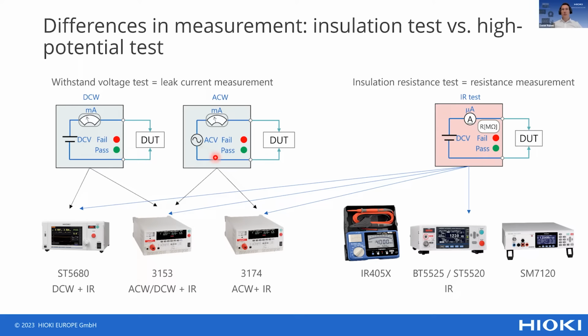While with the withstand voltage test, we have either a DC voltage or an AC voltage being applied to the DUT. We simply only look at the current. So the current resolution is the main interest, because what you want to take care of here is any safety concerns, like users could get some leakage current. So any hazard for the user, this is what you want to exclude when doing a high potential test.